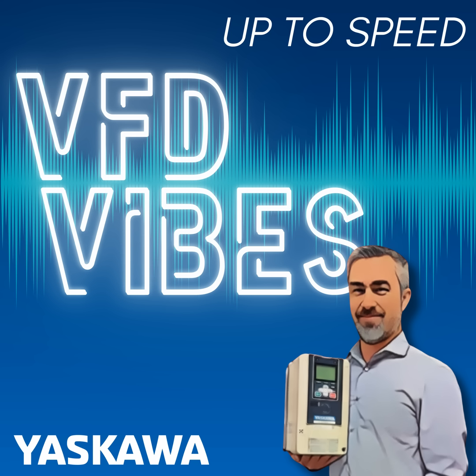A passive harmonic filter is similar to a line reactor in that it has a line reactor, but it also adds a capacitive component as well. And a passive harmonic filter, the designs do vary, but typically provides a tank or a trap for the harmonic currents to be contained between the filter and the drive. Yeah, they work very well.